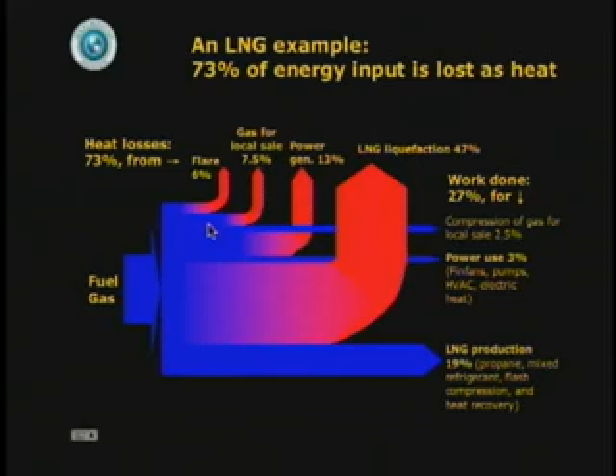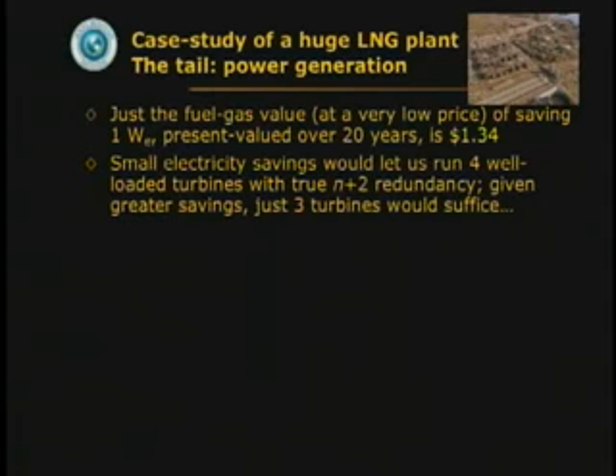Now, if you save a little electricity in this plant, instead of having 5, 6, 7, whatever gas turbines running very inefficiently at part load to provide the power, you could have plenty of redundancy, 2 extra redundant units, running only 4 turbines, but near full load, so they're much more efficient. In fact, with bigger savings, just 3 would be enough. You can also manage loads to achieve this result, like making your liquid nitrogen at night when it's easier.